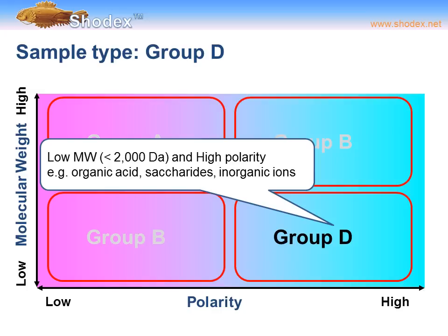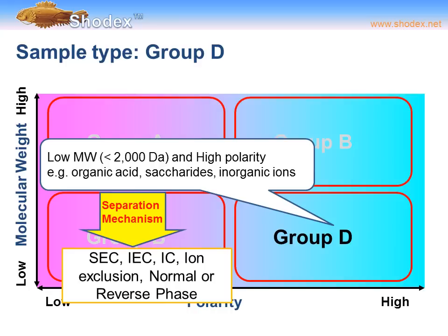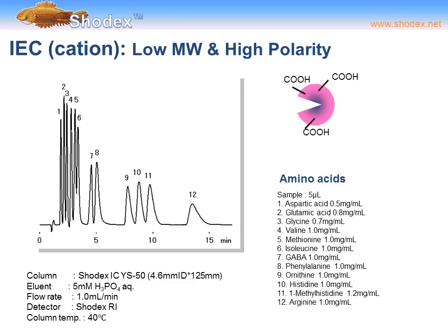This brings us to our final group in the molecular weight versus polarity diagram: group D. These are low molecular weight, high polarity compounds, including organic acids, inorganic ions, and saccharides. The separation mechanism can be SEC, IEC, IC, ion exclusion, or normal or reverse phase. In other words, these compounds are the most diverse and can be separated using the widest variety of columns and separation modes.